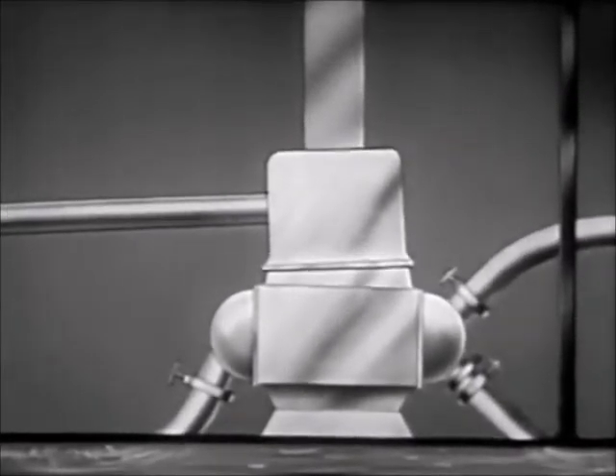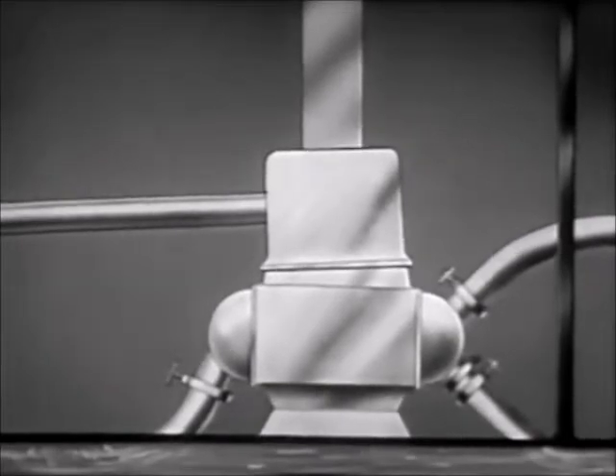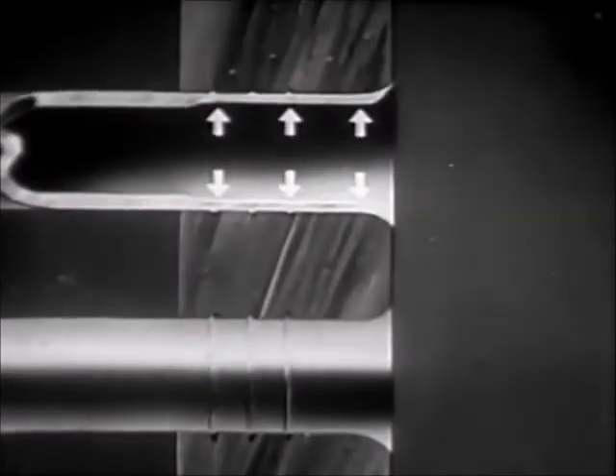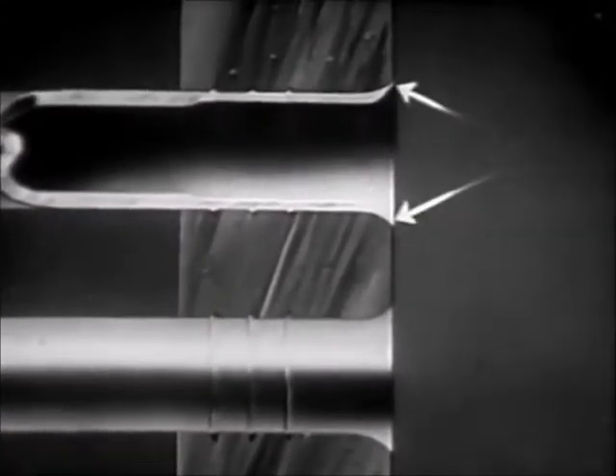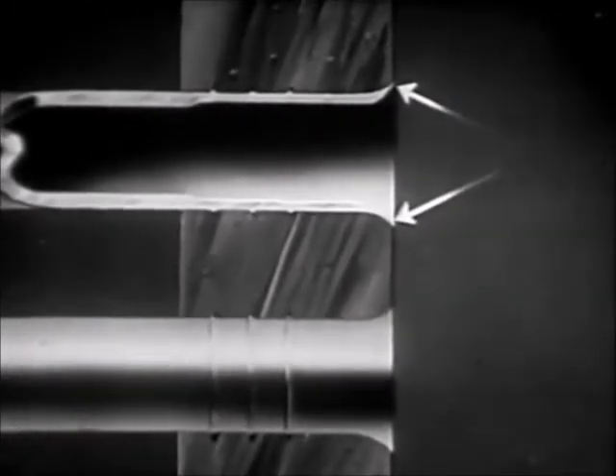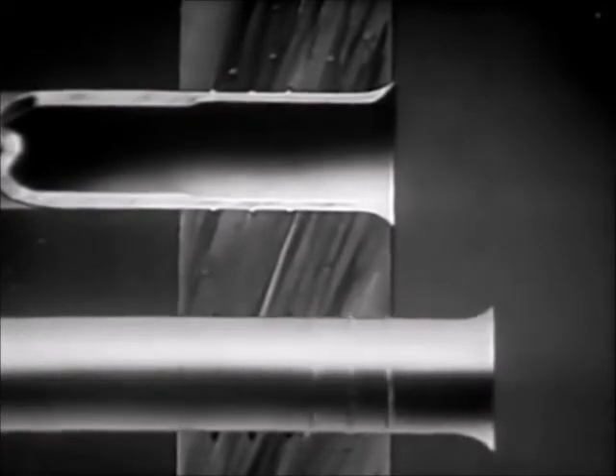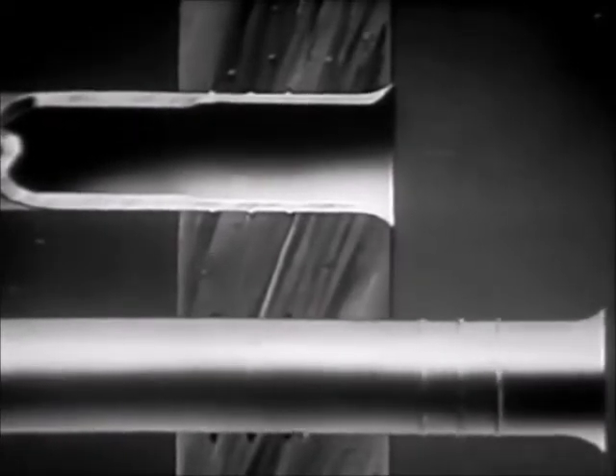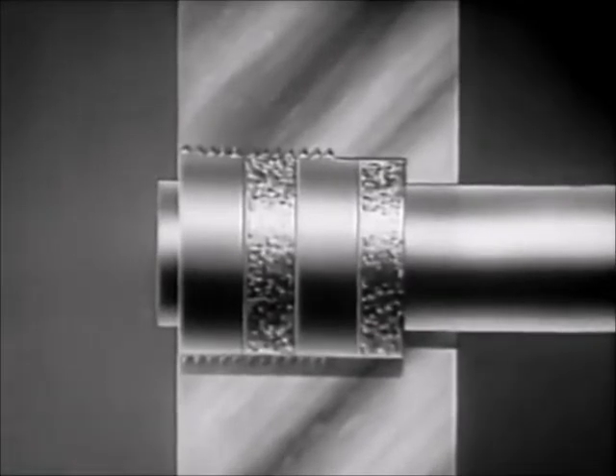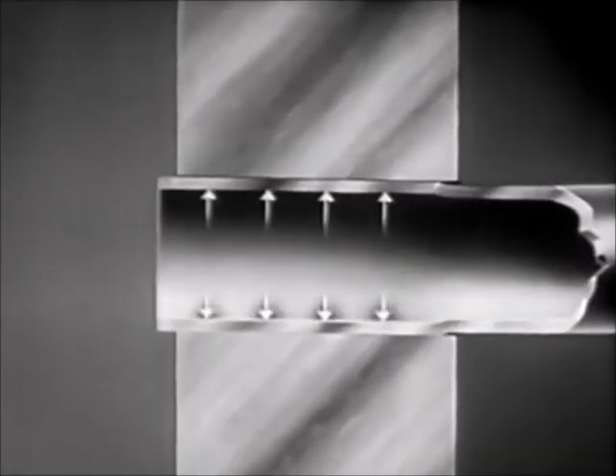The first step in removing tubes is determined by the location of the working space and by the tube joint. In most naval vessels, the tube inflow ends are expanded to form a metal-to-metal joint and flared to streamline the flow of water. Obviously, a flared end can be removed in this direction only. In some condensers, outflow ends are packed. In other condensers, the outflow ends are expanded, but they are never flared.